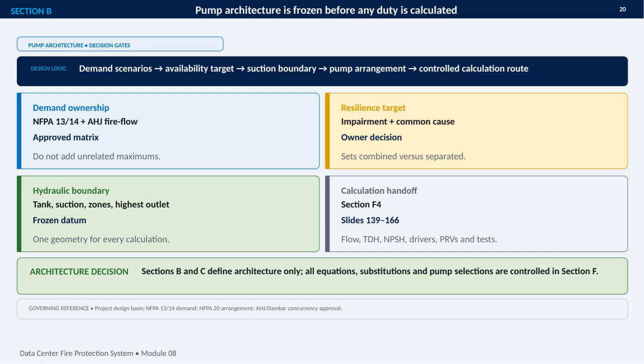This section establishes a critical sequencing rule. Pump architecture is frozen before any duty is calculated. The design logic moves in a controlled order from demand scenarios to the availability target, then the suction boundary, pump arrangement, and finally the calculation route.